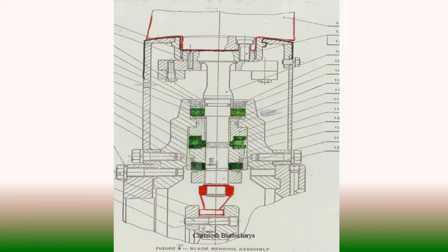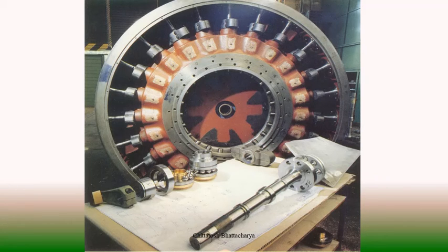blades are connected with an arrangement so that we can have a rack and pinion arrangement. With that, they are all rotating together, and pitches are controlled at the same level. That means if one is rotating by 3 degrees, all the remaining blades are also rotating by 3 degrees this way.